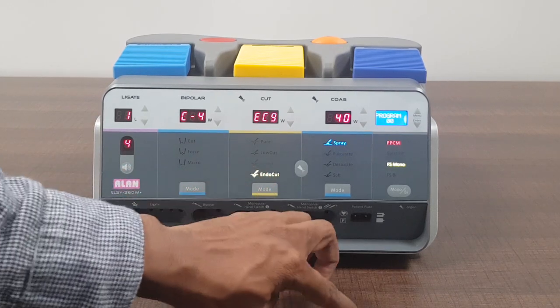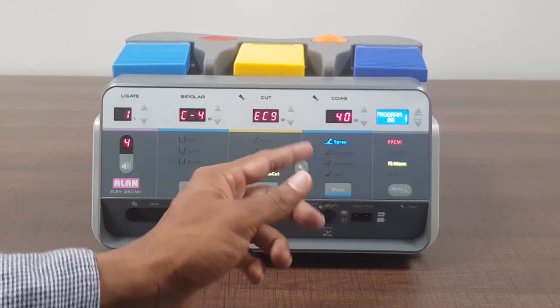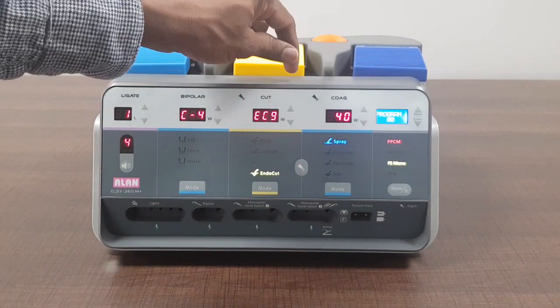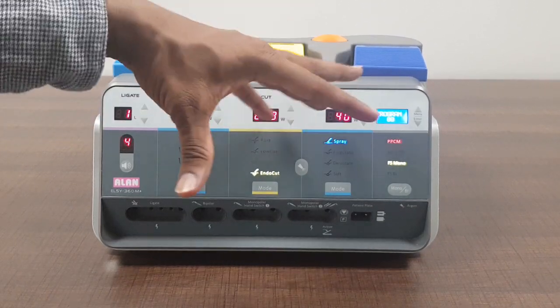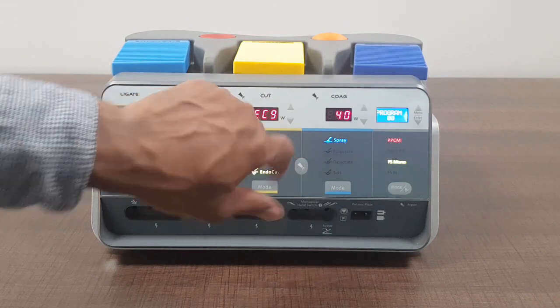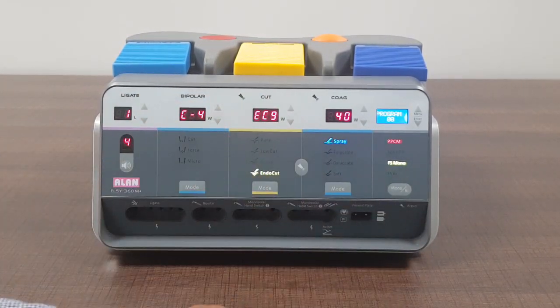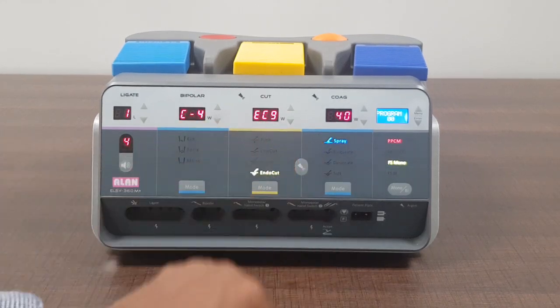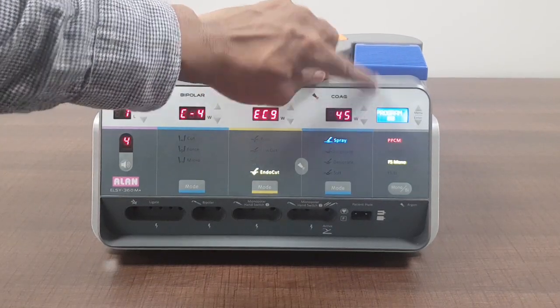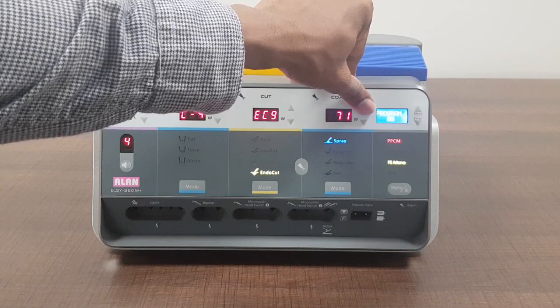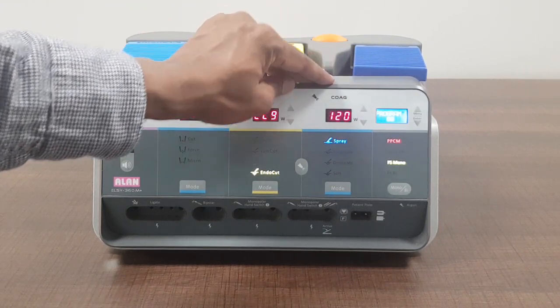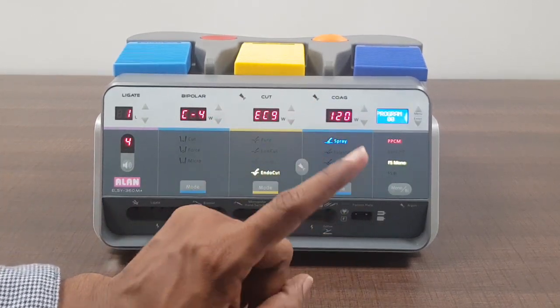When you try to coagulate, if there is any big bleeders like large scars, quite big bleeders, you can use spray. You don't have to touch, just keep it at the distance like this and press spray so it will spray like this. If you can focus on the menu you can understand it sprays just like that. Basically it is used for larger area. Spray gives you superficial coagulation and it is quite widely used in coagulation. The maximum wattage you can go up to is, you see it is increasing, it's 120 watts.